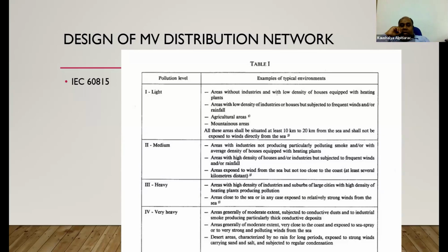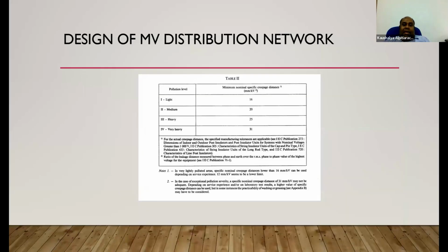Medium, category 2, you have a description there. Heavy is category 3, very heavy is category 4. And this can be categorized into a few applications, like buildings situated near the sea or isolated or away from the sea, and so on. Yes, there it comes, creepage. If the pollution level is very light, you can have a creepage distance of 16 millimeters per kilovolt. If it is medium, the creepage distance shall be 20 millimeters per kV. If it is heavily polluted, 25 millimeters per kV, and very high, 31 millimeters per kV.